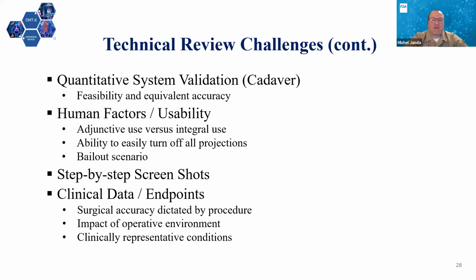This slide discussed some of the additional higher level testing that may be useful to validate these systems. Typically for stereotactic systems, quantitative system-level validation testing is conducted that compares the accuracy between planned implant placement and the final implant placement in a cadaveric model. This has also been the case for AR systems.